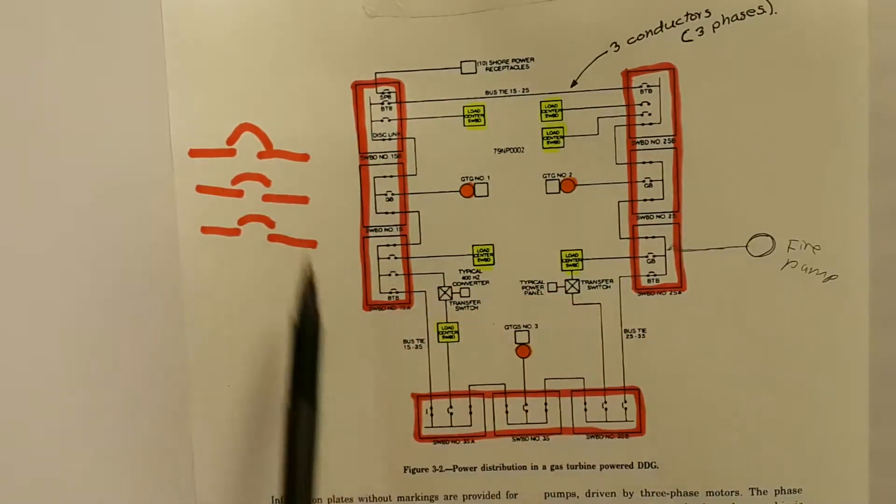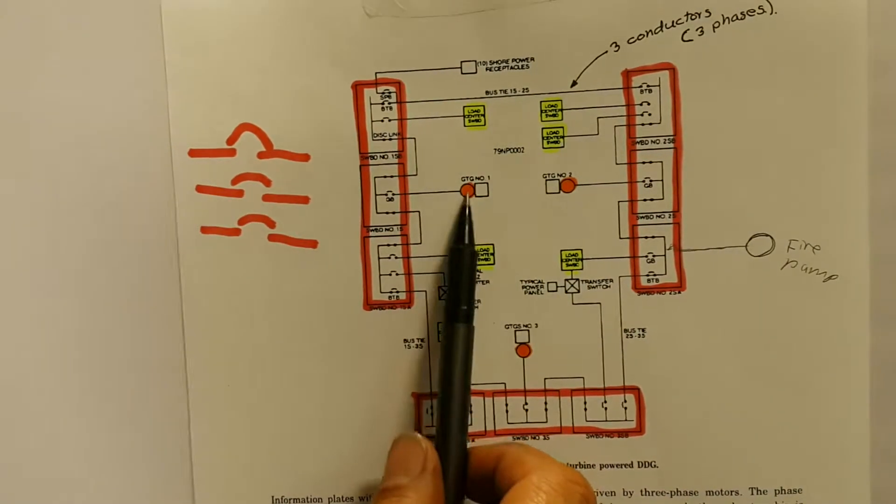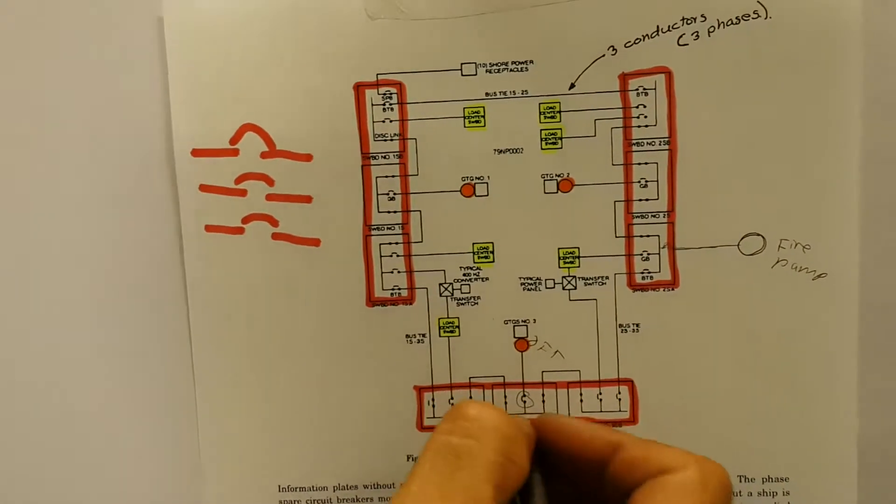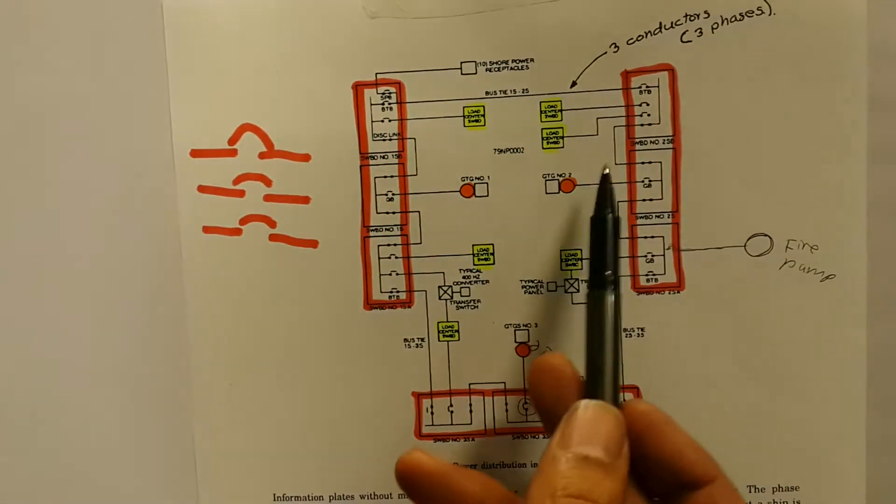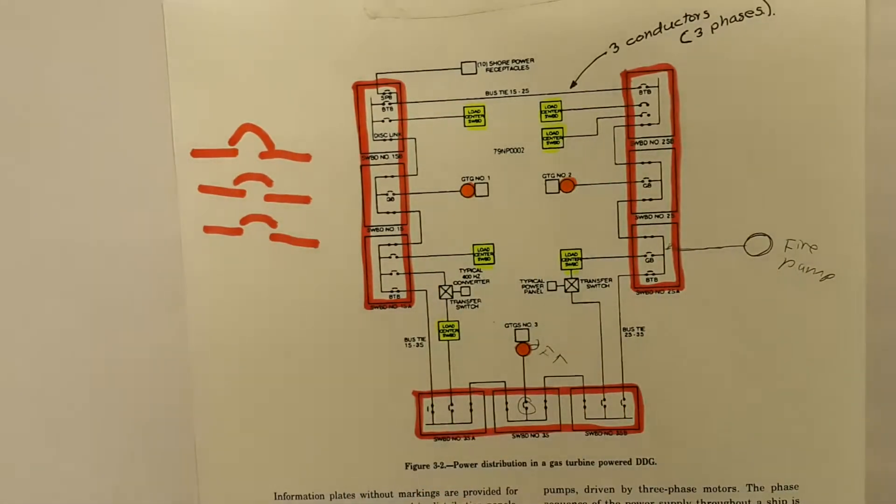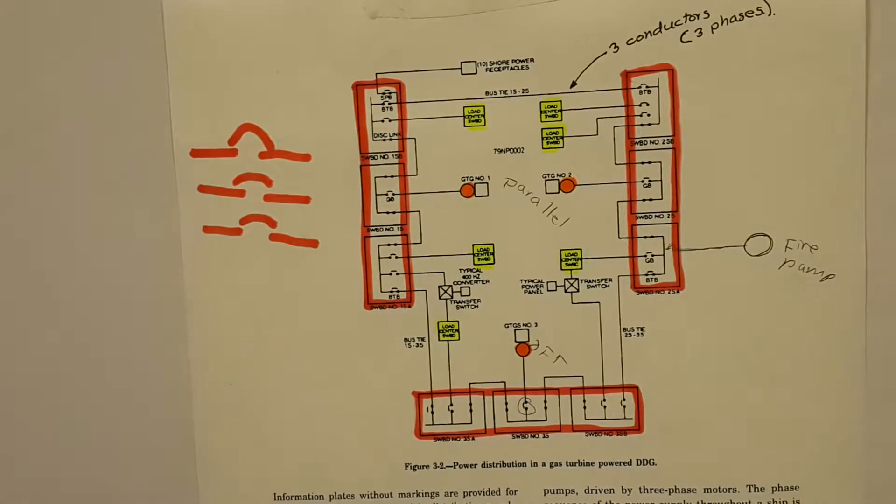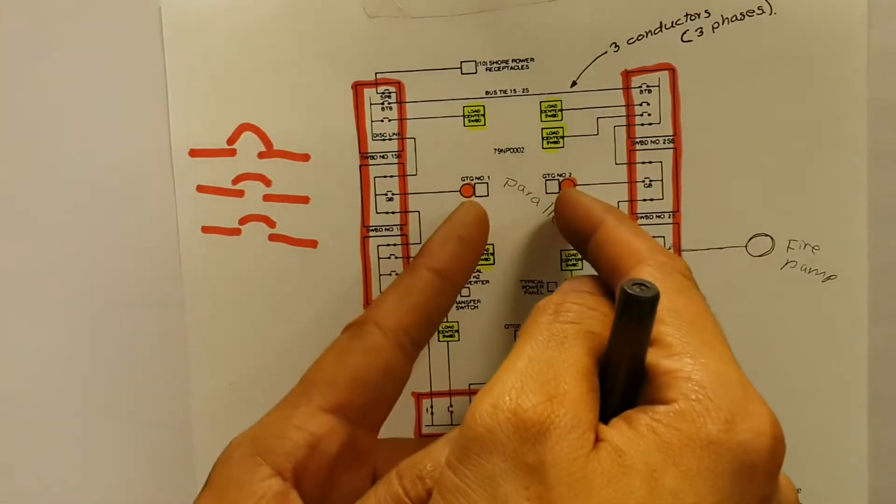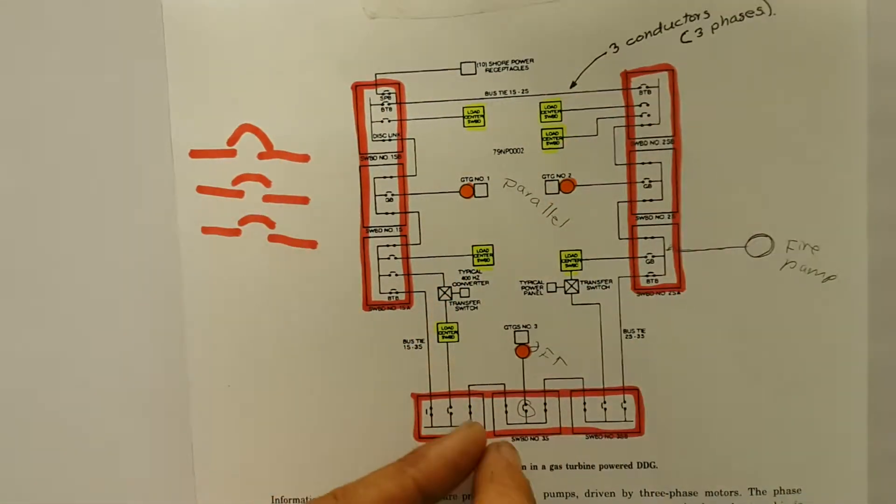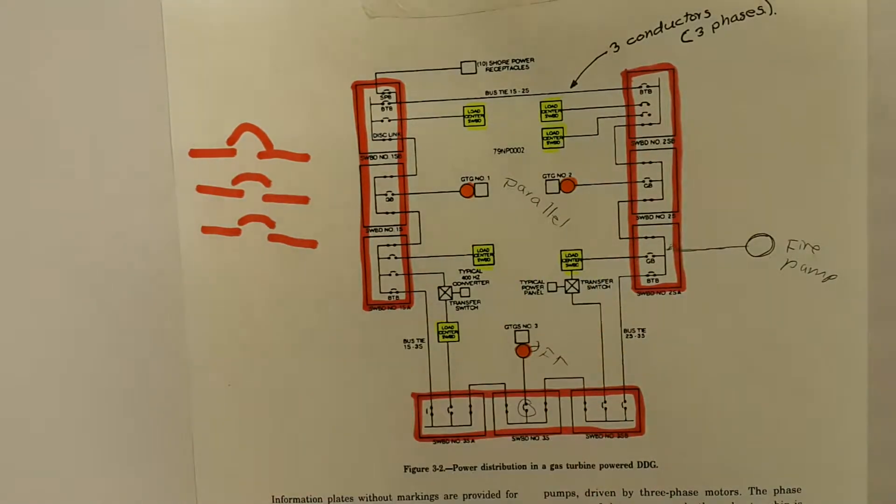That is done whenever you have two generators, let's say one and two on, number three will be off, and this breaker will be open. But one and two can be in parallel. What it means is that, as long as everything is closed with this one open, you will be able to power the entire ship from those two generators.